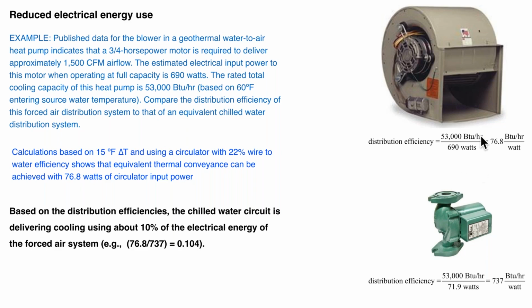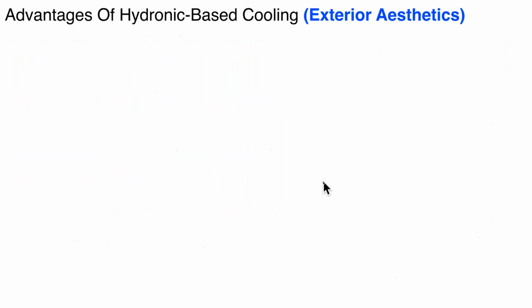So in round numbers, we're at about 1/10 of the electrical energy requirement to move that fluid, liquid water, as opposed to the equivalent cooling capacity being transported using air. And this is true on the heating side as well. It's really one of the underrepresented virtues of hydronic heating, the ability to move energy through a building on relatively low amounts of electricity.